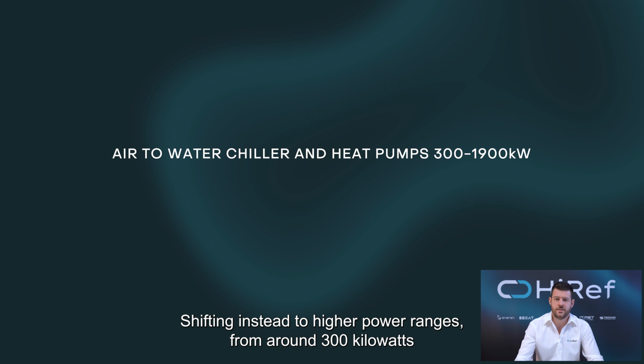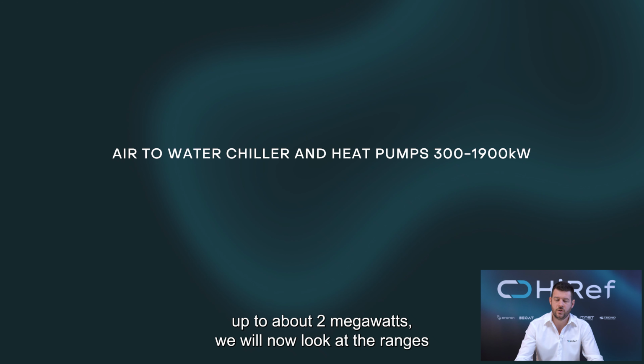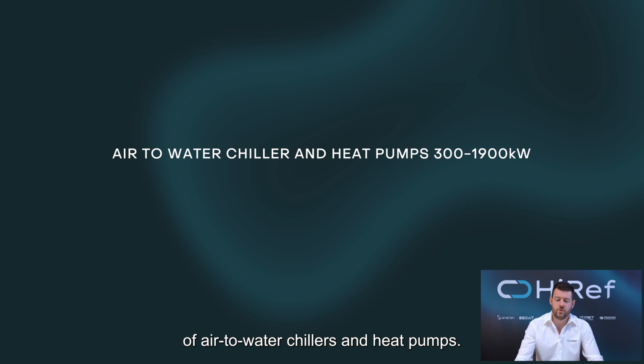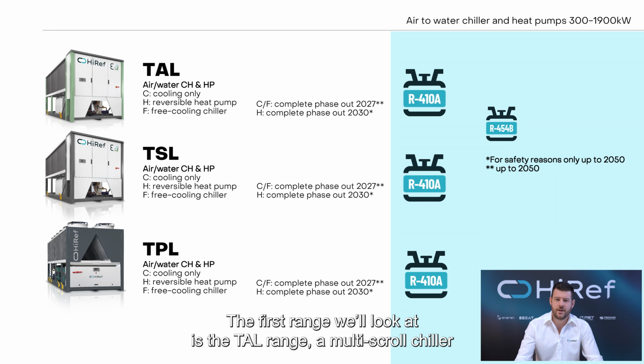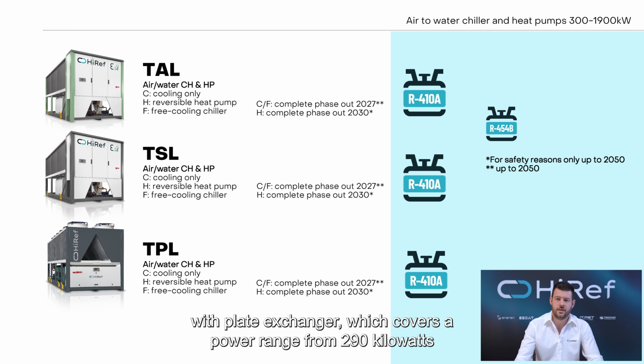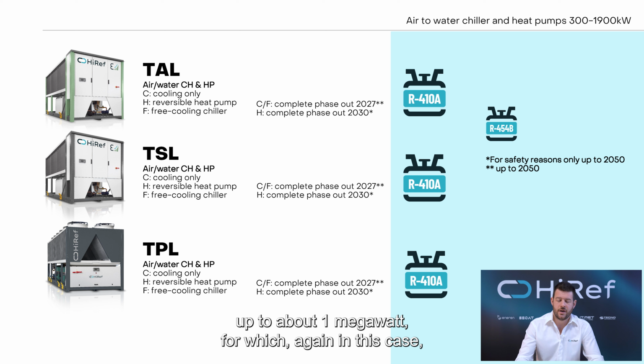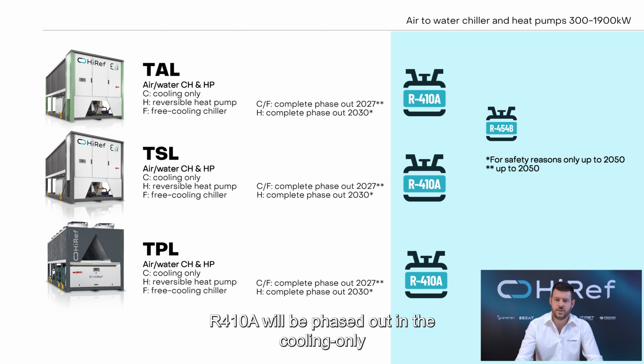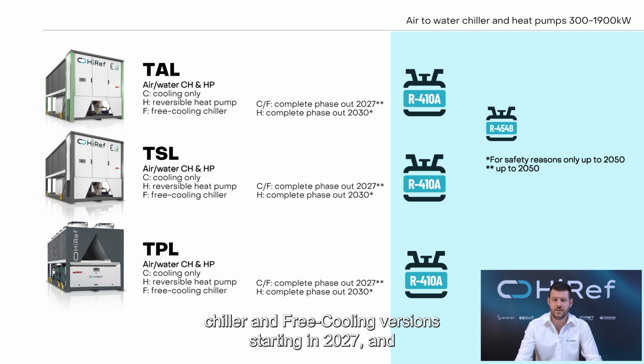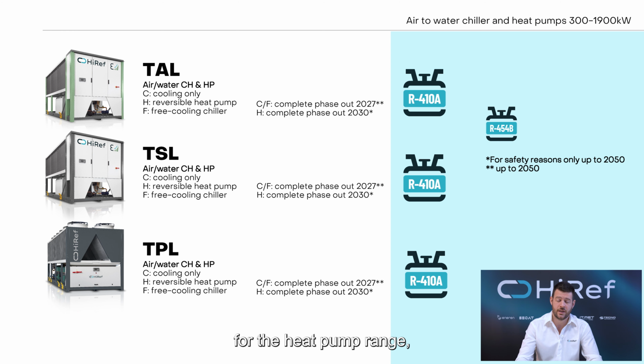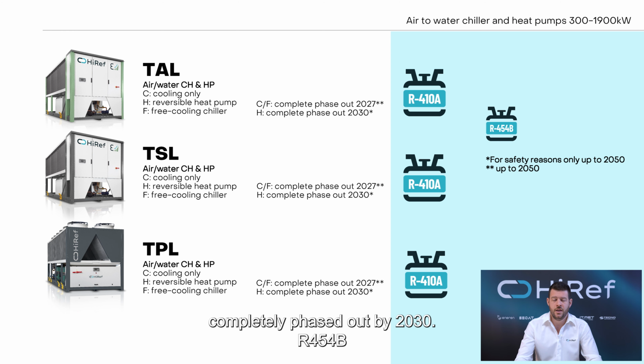Shifting instead to higher power ranges from around 300 kW up to 2 MW, we will look now at the ranges of air-to-water chiller and heat pumps. The first range we'll look at is the TAL range, a multi-scroll chiller with plate exchanger which covers a power range from 290 up to about 1 megawatt, for which, again, in this case, 410A will be phased out in the cooling-only version, chiller and chiller with free cooling version, starting from 2027. For the heat pump, completely phased out by 2030.